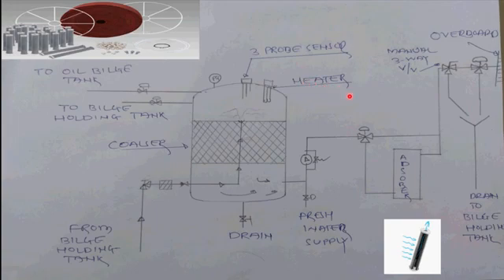So once all that process is done, what happens next? Once oil is detected in the water, the process gets stopped. After accumulation of oil, a sensor senses the oil content, and if oil is present, the pump stops and fresh water gets in for back flushing. The fresh water pushes up the oil, this valve opens, and the oil gets back flushed to the oily bilge tank.